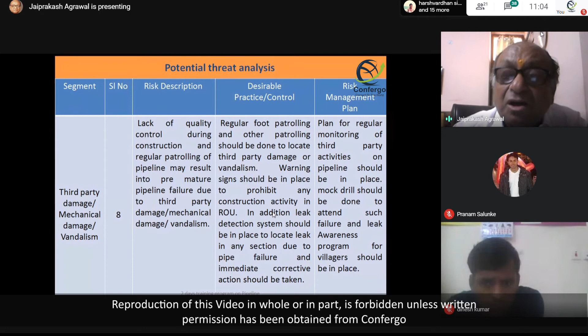Oil producing and oil transporting companies require this very much, because of third party damage, theft of oil and pilfering of oil. So they need a very robust system to monitor any undue activities on the pipeline. You have different systems available, whereby you can monitor through satellite data transmission, or some sort of vibration monitoring system. If there is some undue activity, that vibration signal comes in the control room, and they can know something unwanted is happening. Also there is a leak detection system. If there is any leak in the pipeline, that can be known through your pressure differential system or your acoustic emission system.